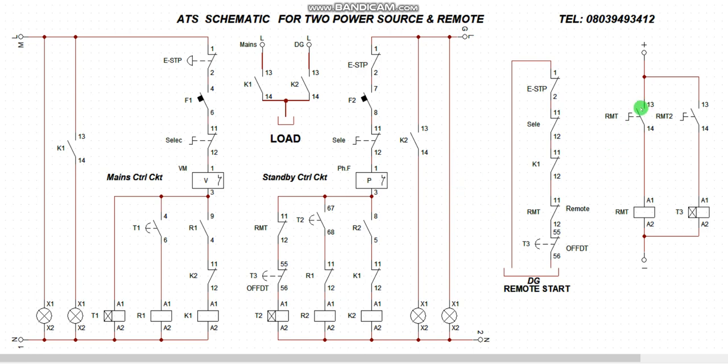One is the remote control here to control the genset. Another one is a timer function to control the same genset. The reason is this particular logic is for the standby supply. The standby supply will shut down, but it will be subject to the availability of the utility supply. It cannot shut down until utility is available to shut it down.